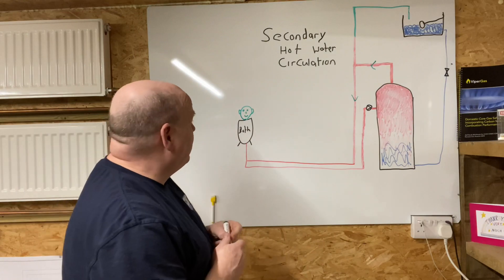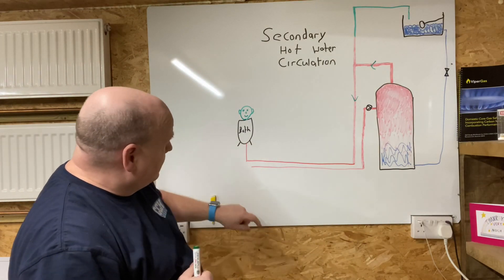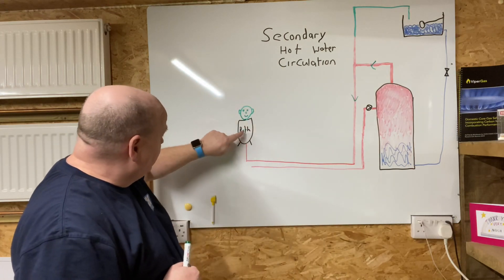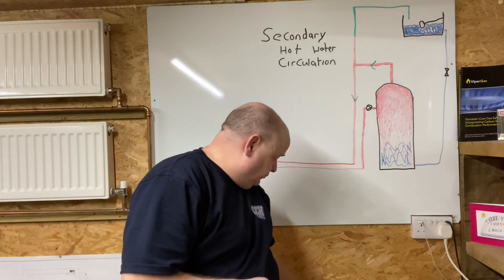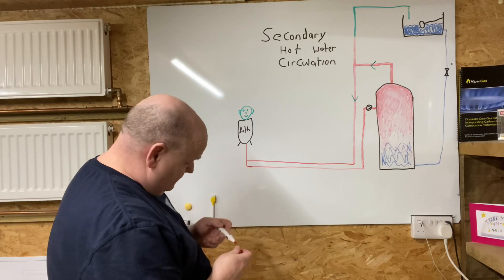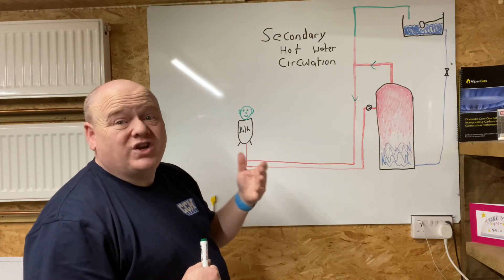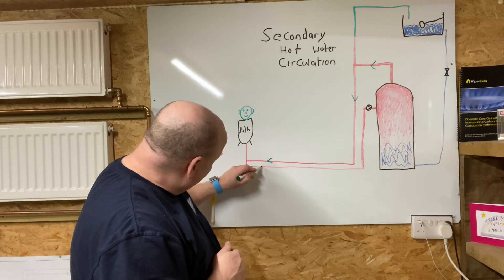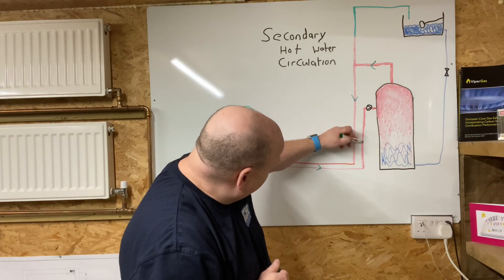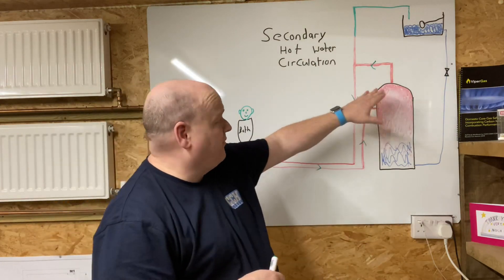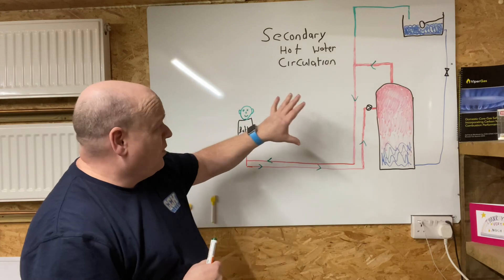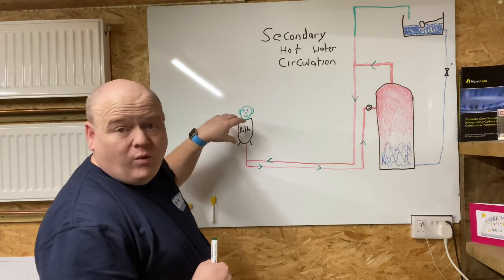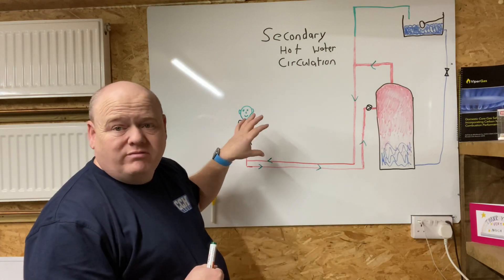On a normal system without a return, when you run this bath you've got to wait until the hot water travels all the way around to the bath. But what this pump does — when we connect this back up to the cylinder — it circulates the water all the way around, going this way and back into the cylinder. So it's circulating this hot water so that when you open the tap, the hot water is almost instant.